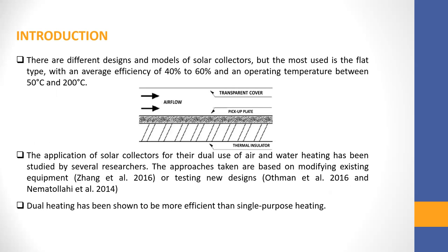There are different designs and models of solar collectors, but the most used is the flat plate with an average efficiency of 40% to 60% and operation temperature between 50 and 200 degrees Celsius.